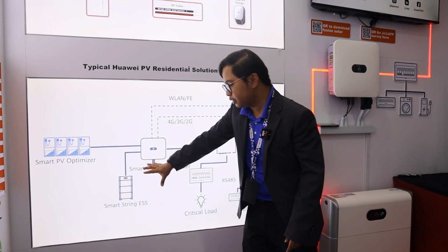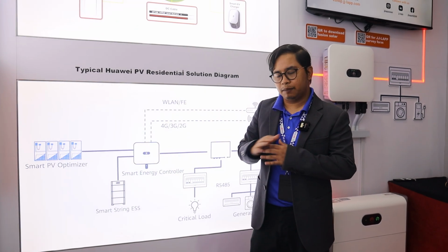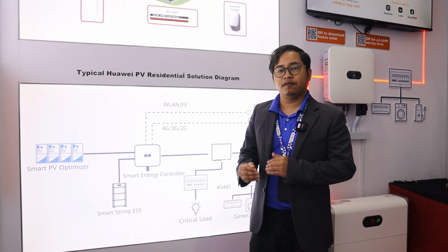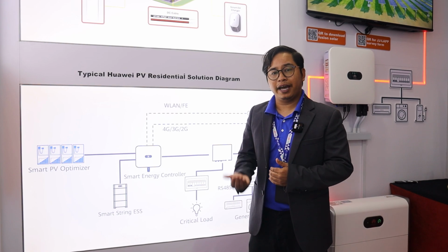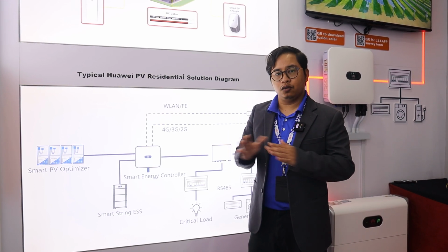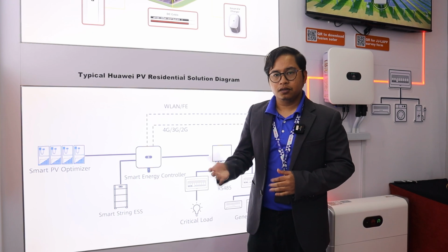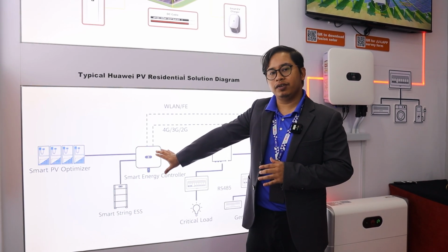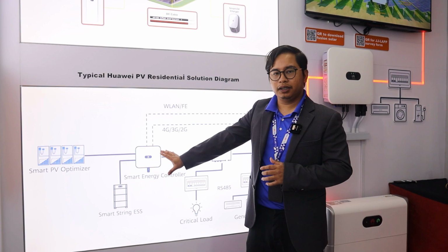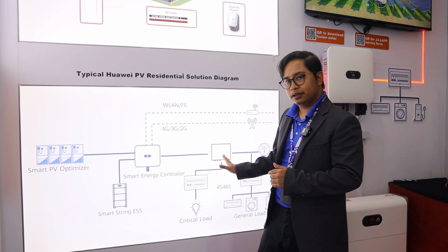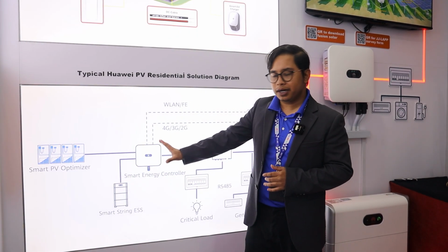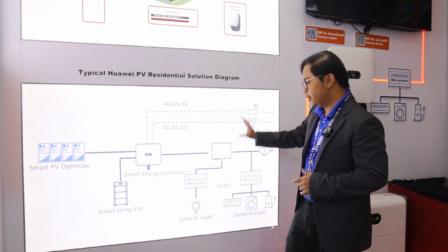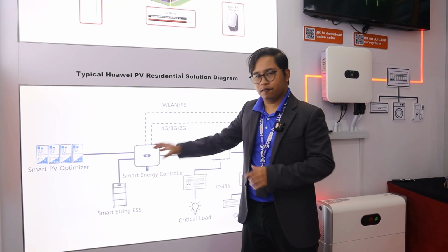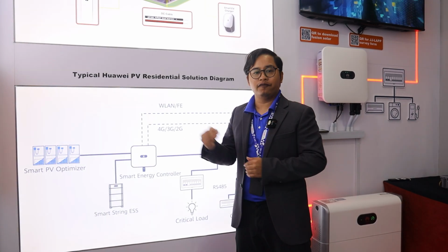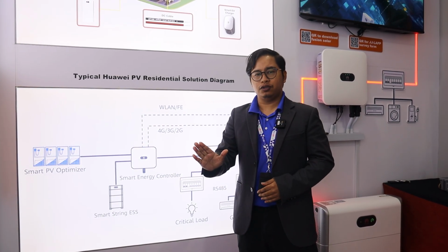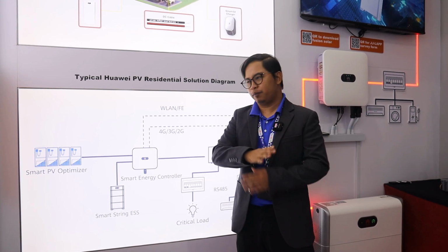If we look at a typical solar system, it doesn't consist of a battery. What happens if you don't have the battery? When there is a grid outage, meaning a blackout, because the PV is an on-grid type, when there is no AC detection, the inverter will shut down. But if you install the battery with the backup box, it will convert from on-grid mode to off-grid mode. So during a blackout, there is no issue - you still have electricity compared to your neighbor.